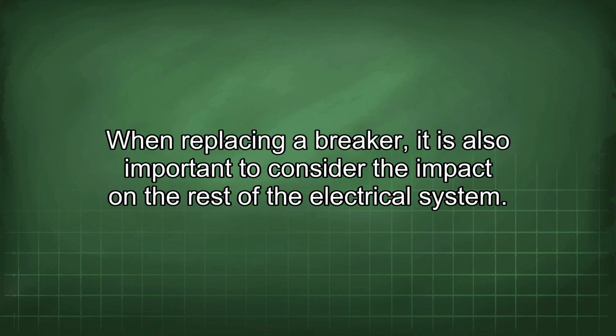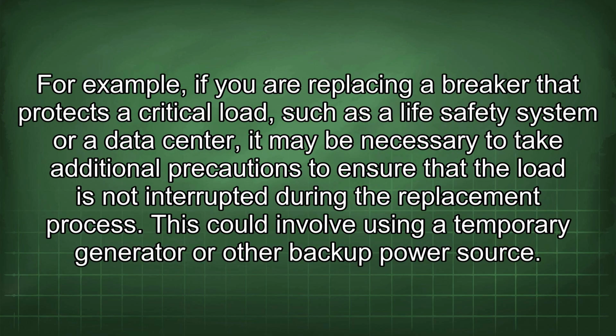When replacing a breaker, it is also important to consider the impact on the rest of the electrical system. For example, if you are replacing a breaker that protects a critical load, such as a life safety system or a data center, it may be necessary to take additional precautions to ensure that the load is not interrupted during the replacement process. This could involve using a temporary generator or other backup power source.